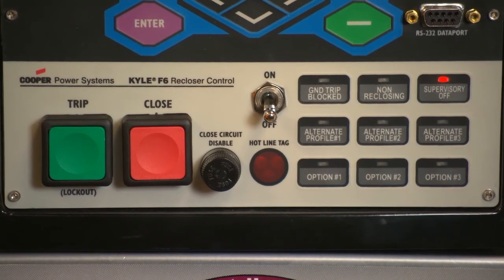Hotline tag is provided for live line work applications. All closing operations are disabled when the hotline tag feature is activated. While active, the control utilizes an independent, user-selectable time current curve for trip operations. Important: hotline tag activation does not cause the recloser to trip open. It only prevents the recloser from closing.